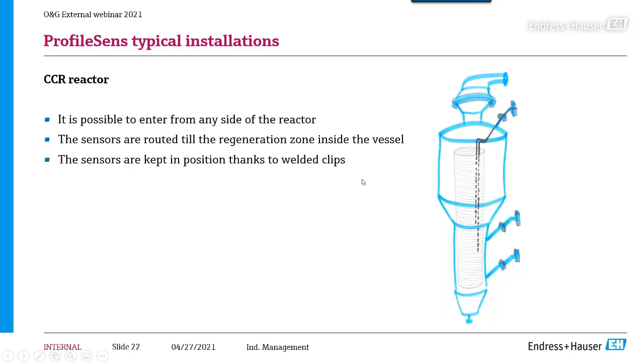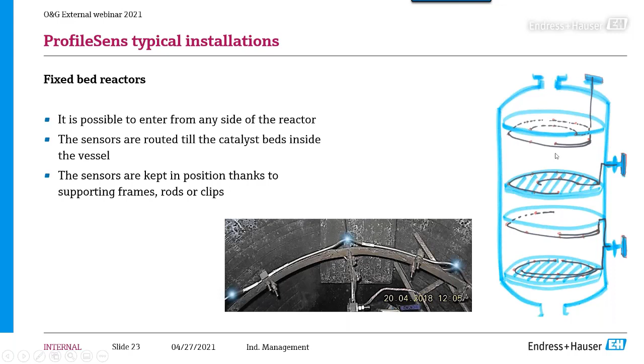When we refer to fixed bed reactors, we can also provide very interesting solutions. We can enter from the top, like in this picture, or from the side. Normally, by means of supporting rods hanging from the distributor trays, or a supporting frame fixed to the main beams of the reactor, like in this picture, we can keep all the thermocouples in the right positions inside the reactor, including the new ProfileSens reactor.